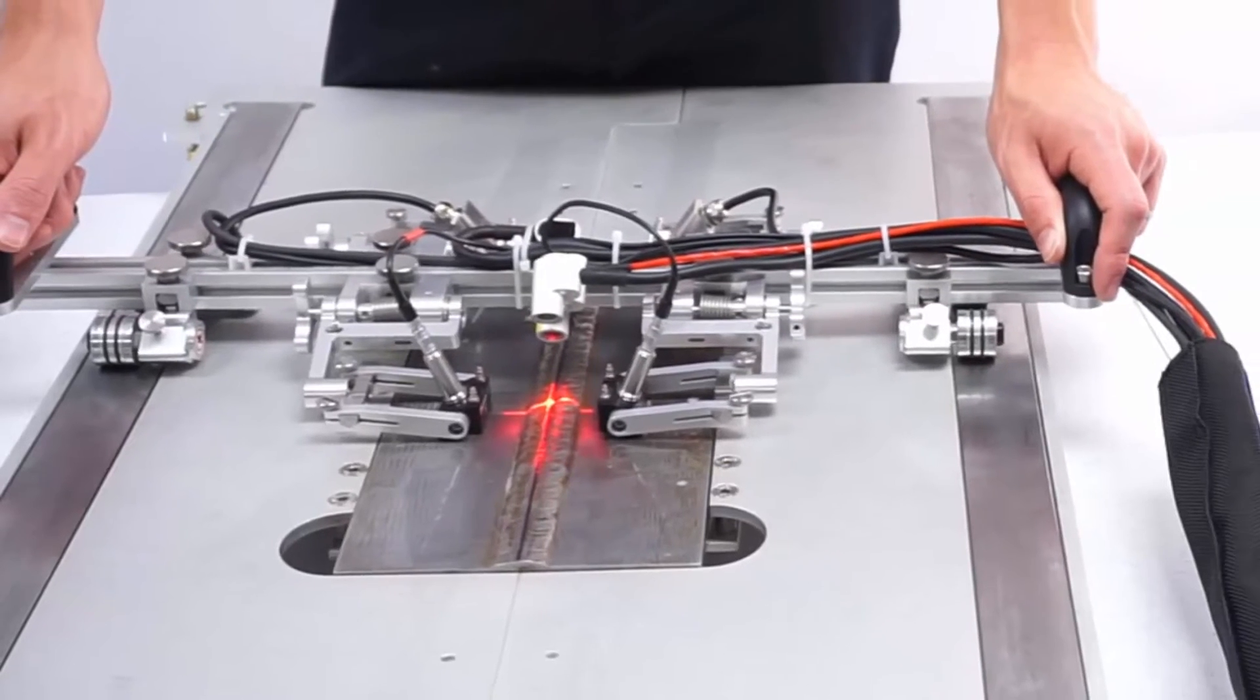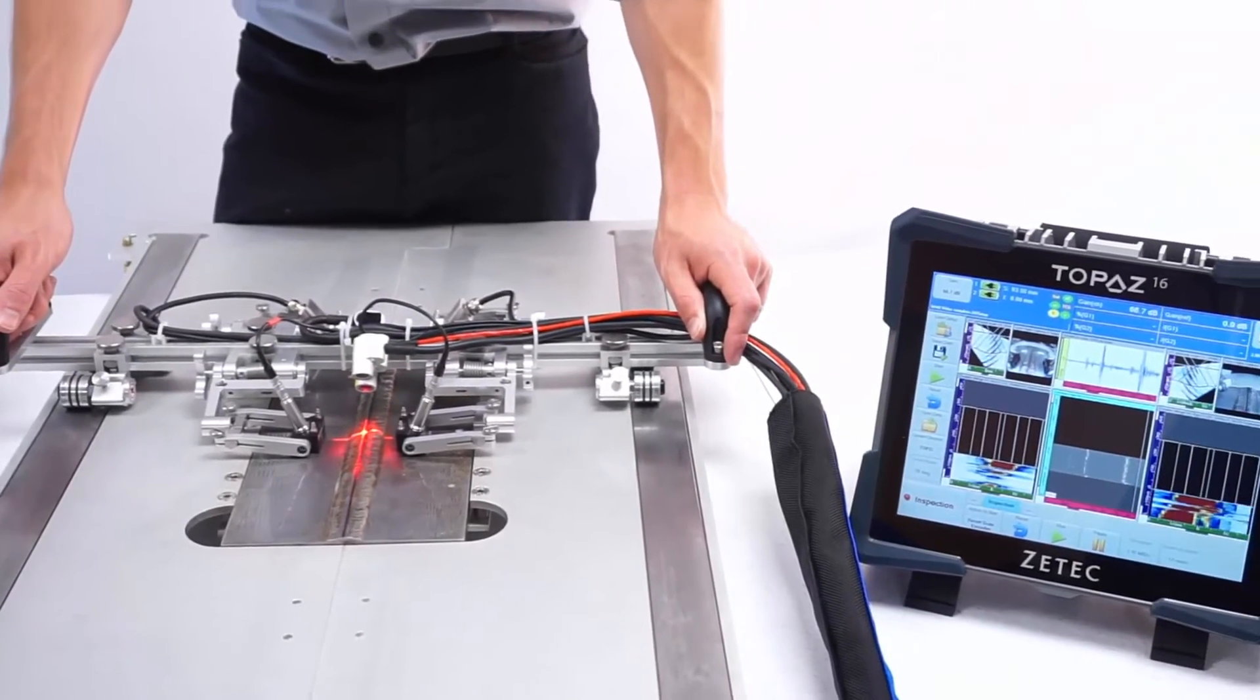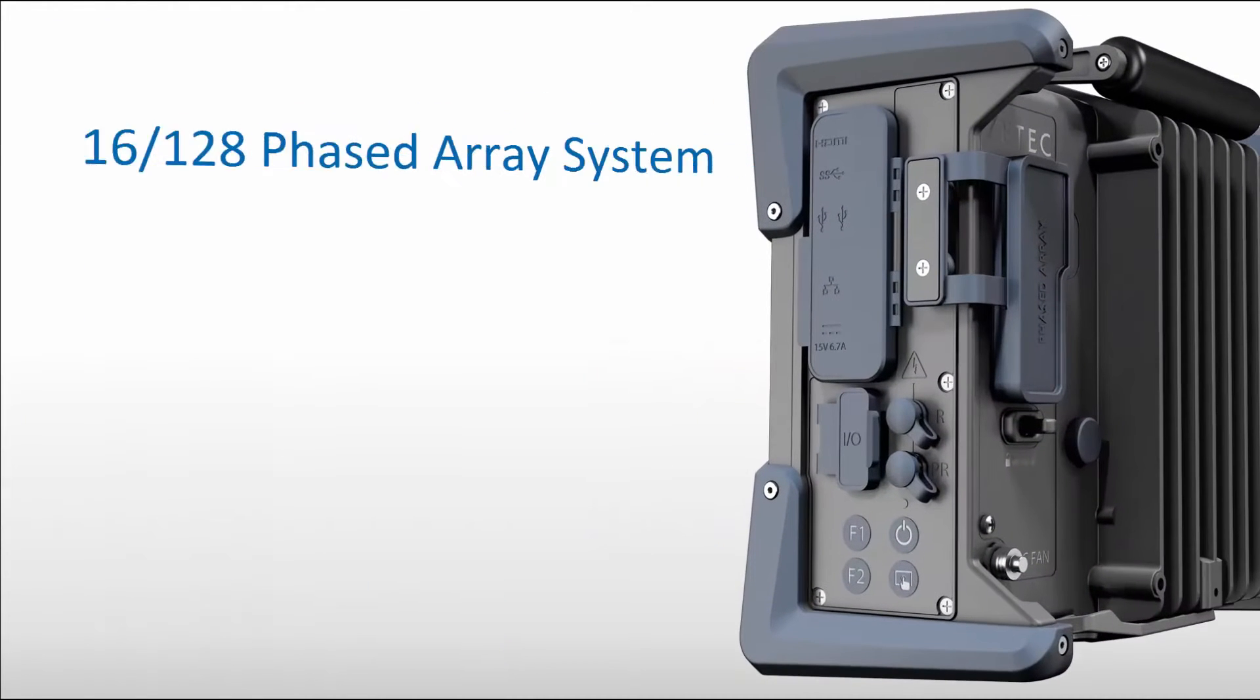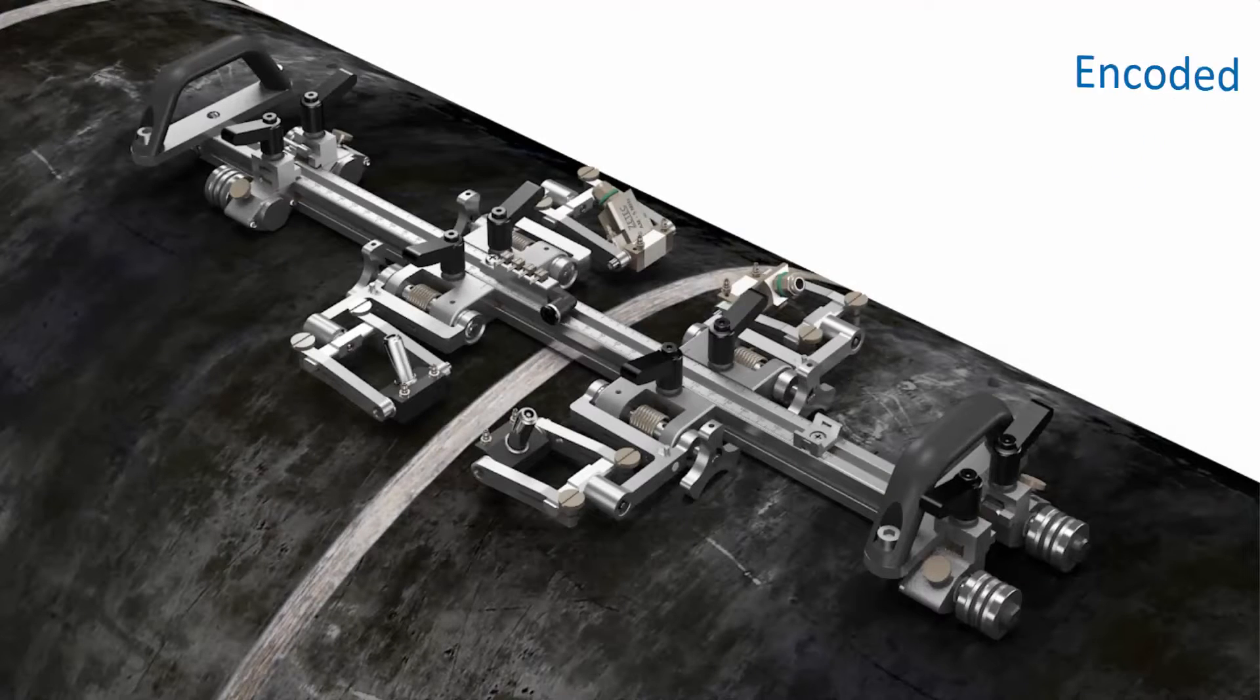These complementary techniques result in high probability of detection for a wide range of welding defects and excellent sizing capabilities for critical planar flaws. Topaz 16 is a fully integrated portable phased array unit that delivers big value in a small size. It's a 16-128 phased array system with a separated conventional UT channel at 200 volts, controlled by the powerful and user-friendly ZETEC UltraVision Touch software platform.